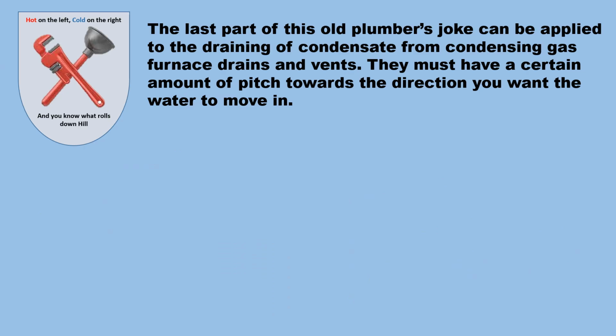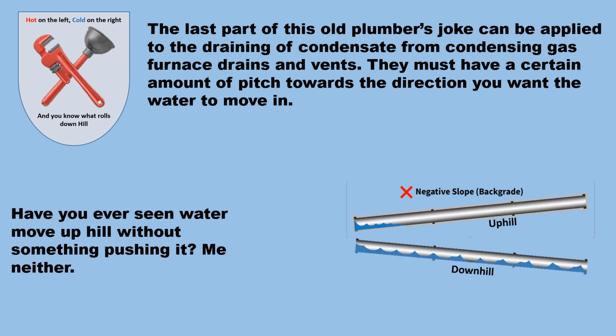The last part of this old plumber's joke can be applied to the draining of condensate from condensing gas furnace drains and vents. They must have a certain amount of pitch towards the direction you want the water to move in. Have you ever seen water move uphill without something pushing it? Me neither.